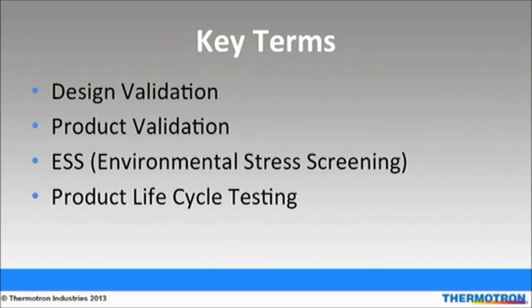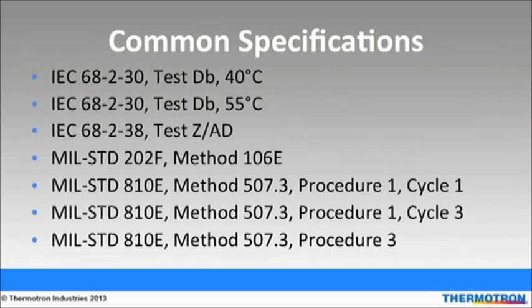Product life cycle testing simulates real-world stresses in order to predict the lifespan of the product. Thermotron manufactures for these four types of tests by simulating actual field environments like temperature and humidity. Many products go through standard testing procedures that are widely accepted including those from the military, IEC, UL, and IEST. Thermotron's 8800 programmer controller includes 10 pre-programmed tests including four MIL-STANDARD and three IEC profiles.